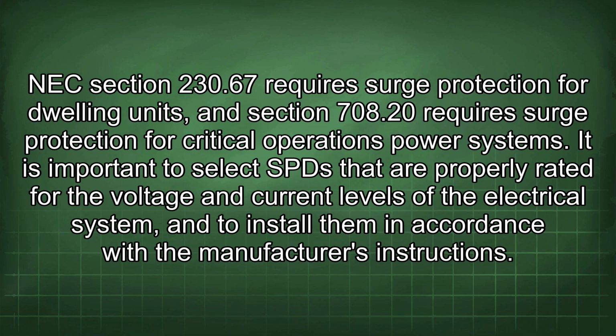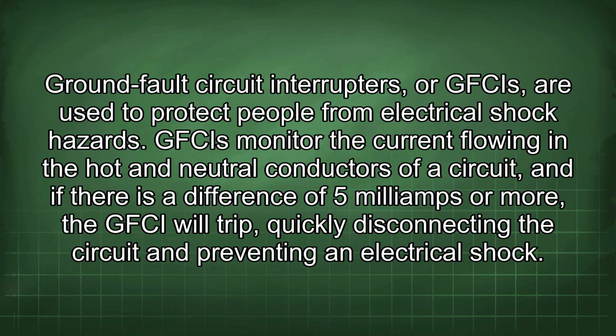It is important to select SPDs that are properly rated for the voltage and current levels of the electrical system, and to install them in accordance with the manufacturer's instructions. Ground fault circuit interrupters, or GFCIs, are used to protect people from electrical shock hazards. GFCIs monitor the current flowing in the hot and neutral conductors of a circuit, and if there is a difference of 5 mA or more, the GFCI will trip, quickly disconnecting the circuit and preventing an electrical shock.